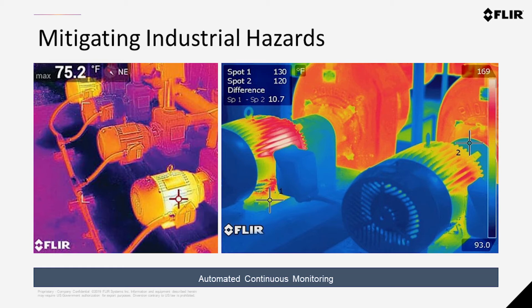Then you could use that to identify trends over time. Let's say, for example, we've got this row of motors and they're all operating similar systems at similar load. If you suddenly see one motor running hotter than the other two, this can be an early indication that something is wrong. And again, as our motor experts discussed this morning, it doesn't necessarily mean there's something wrong with the motor. It might be something else in the drivetrain. But it does indicate, hopefully early enough that you can plan an outage and not be caught by surprise, that it requires more troubleshooting.